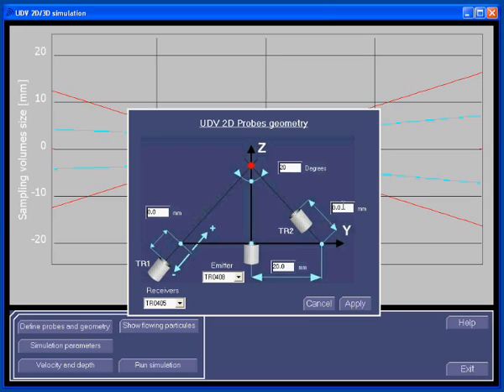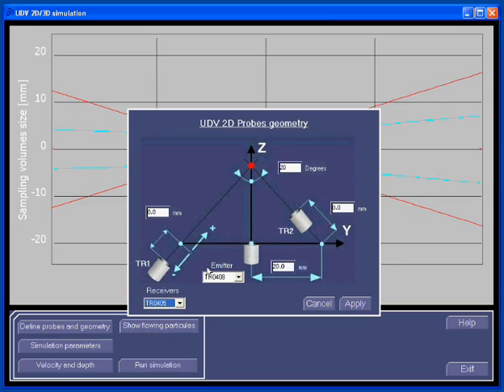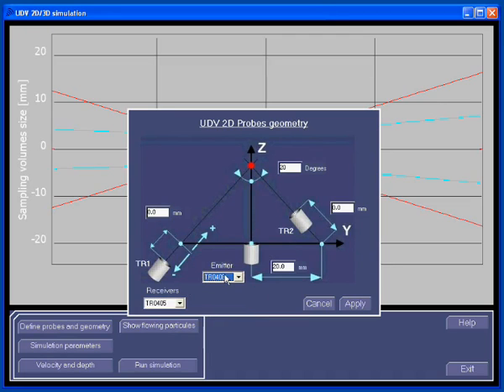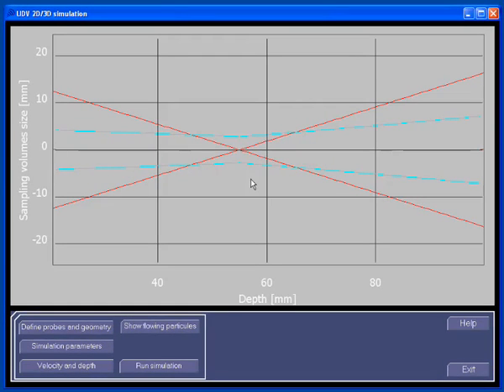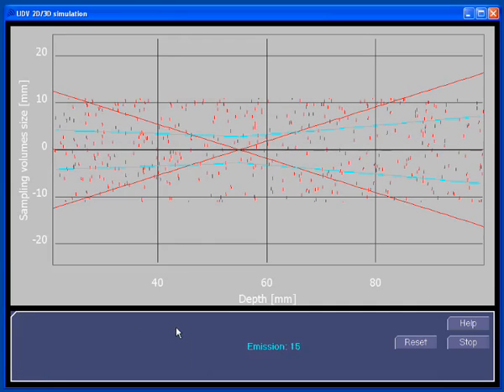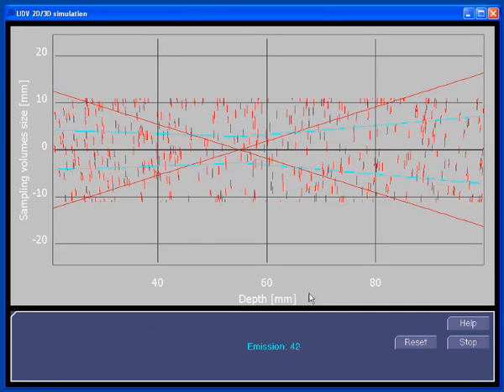The emitting probe and the receiving probe can be selected from a list of available transducers. For a receiver, let's select a 4 MHz 5 mm, and for the emitting probe, a 4 MHz 8 mm transducer. For all probes, the operating frequency must be the same. Before doing our first simulation, let's have a look at how the particle flows. A click on that button shows the flowing particles. Every reset, we start a new visualization.